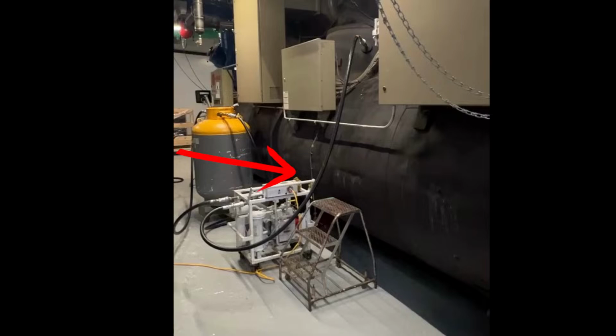What this machine is doing is the recovery machine is drawing a slightly lower pressure, or I mean, it's all in a vacuum in the end, on this recovery cylinder. This recovery cylinder should have already been pulled into a vacuum prior to starting this recovery. So once you open the valves, you should be at an evacuated state where it's going to start drawing liquid refrigerant in directly off the bottom of the evaporator.